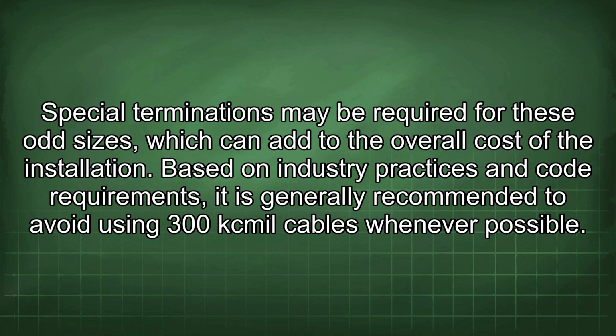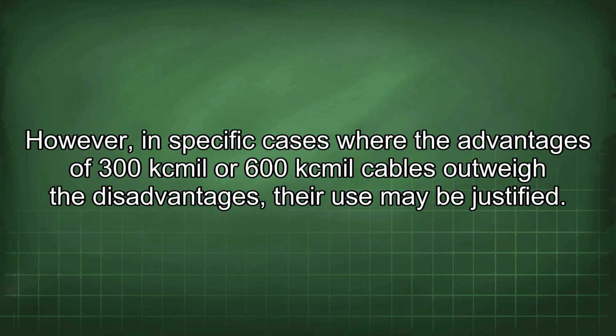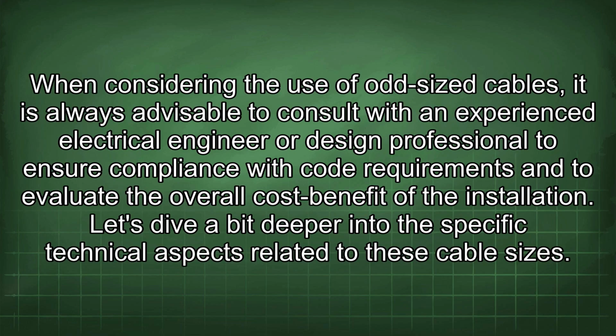Based on industry practices and code requirements, it is generally recommended to avoid using 300kcmil cables whenever possible. However, in specific cases where the advantages of 300kcmil or 600kcmil cables outweigh the disadvantages, their use may be justified. When considering the use of odd-size cables, it is always advisable to consult with an experienced electrical engineer or design professional to ensure compliance with code requirements and to evaluate the overall cost-benefit of the installation.